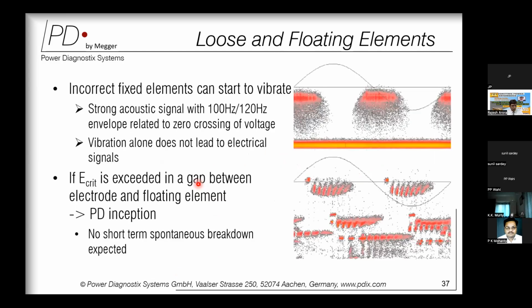Like if you have some connection issue, or some loose connection, the pattern will be generated similar to this, and it will be mostly related to zero crossing voltage and generating a vibration at typically 100 or 120 hertz. And if the gap at this loose connection is more than the electric field of the insulating material can withstand, then it will start the inception of PD, and then you can see a different kind of PRPD pattern. So if it is not crossing the electric field, you can capture it using an acoustic sensor. If it is crossing the electric field, then there will be a partial discharge which you can capture using a UHF sensor.